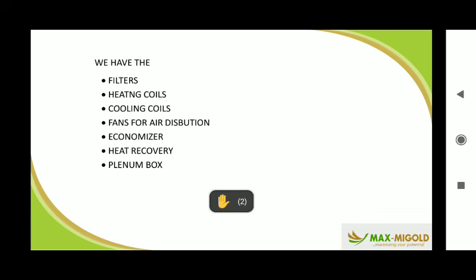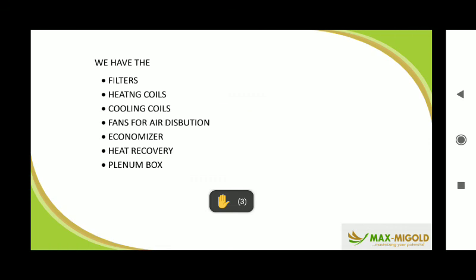Sometimes they tell you one AC is 1 horsepower; that 1 horsepower is the same as 2.8 kilowatts. Are you getting me? So you can get it from the nameplate or by mere looking, but the nameplate gives you a precise capacity, showing the cooling capacity and the electrical capacity. Please do not confuse electrical power with cooling power.